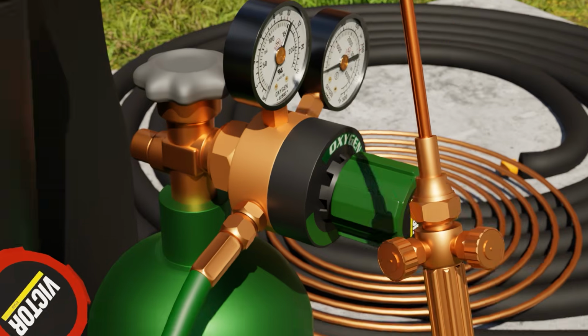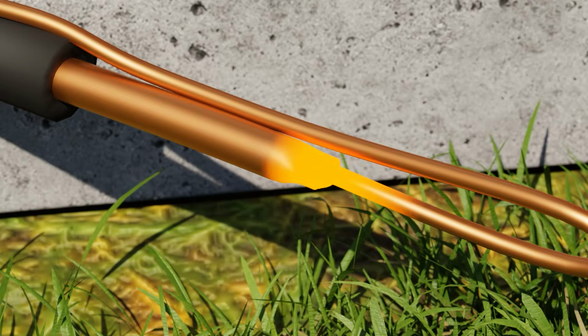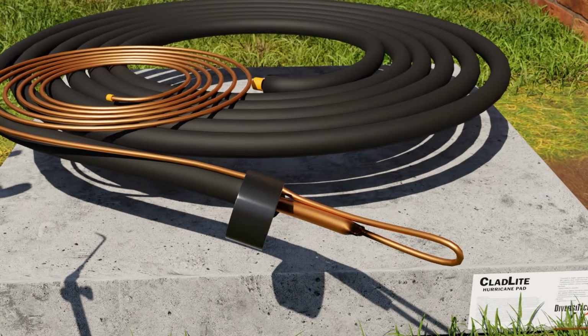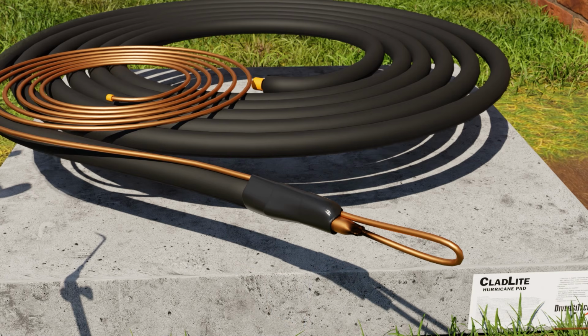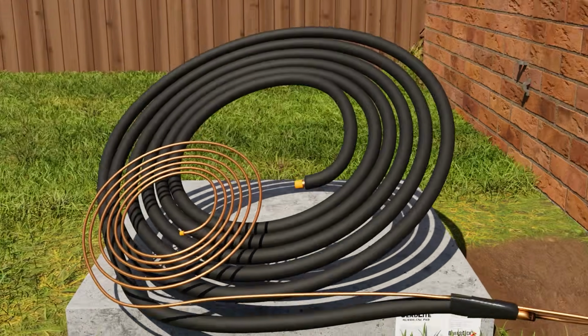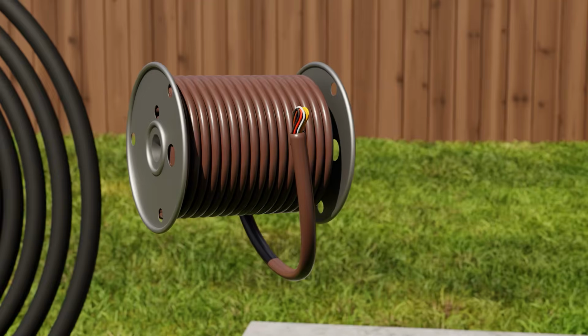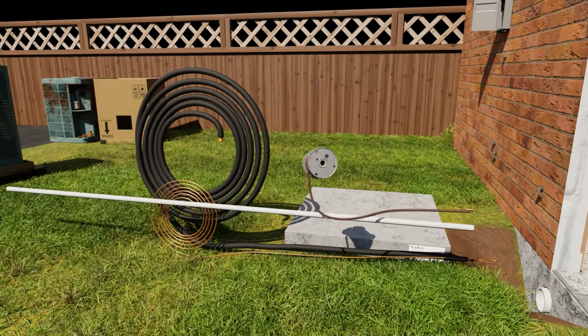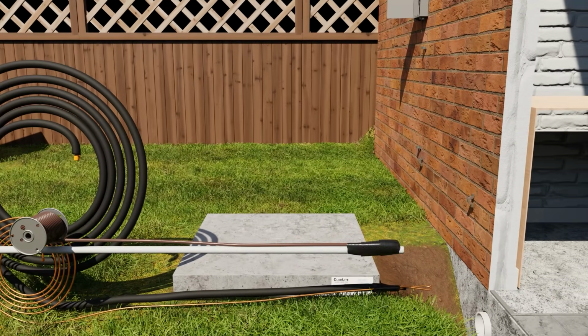Now we're going to shut off our tanks and our regulators, allow our copper to cool, and tape up the ends so they don't get damaged as we pull them through. We're also going to attach our thermostat wire to our drain. In some cases, some people run them together all the time. Some people run them separately. Do whatever works for the application.